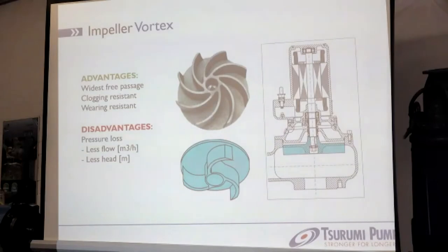The disadvantages are pressure losses because we are talking about a pump with a wide free passage. This results in less flow compared to channel impellers and less head compared to channel impellers or multi-stage impellers. We are definitely talking about the lowest hydraulic efficiency among the impeller types you can find.